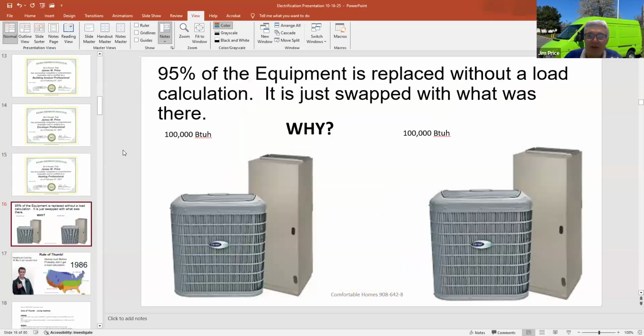95% of the equipment replaced today is done without a load calculation. This is so important because when equipment was originally installed by the builder, remember it was the cheapest one they could find, it also wasn't efficient. There was equipment installed, and I'll give you a timeline later, that was about 50% efficient prior to 1992, meaning you paid a dollar for gas and got 50 cents worth of heat. Efficiency standards were set in 1987, so if your house and equipment were installed before 1987, there were no standards of efficiency, you were just buying junk.